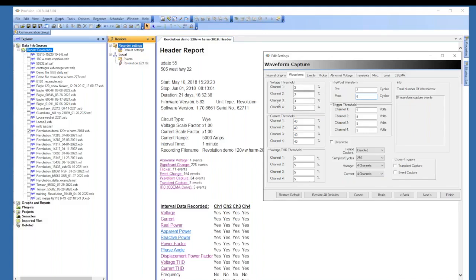Your triggers are voltage threshold by percentage, and this is a cycle-to-cycle change. So in a template, if you can use it for 120 or 277, setting it up by percentage works better. And then it's going to choose the lower of these. You can also record on absolute voltage. So if you kick these up higher, then you know that it's always going to be 3% of the voltage change. Or if you want a specific one, you can set up 15 volts, something like that, and then choose your percentage a bit higher. But it's going to choose the lower of those two when it's triggering.